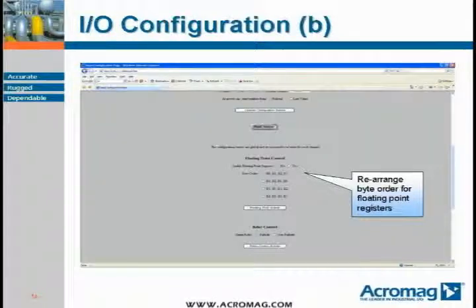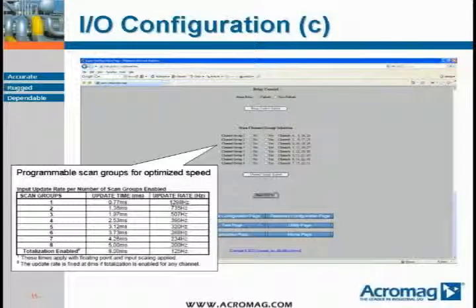By default, the output bytes for each channel are transmitted according to the IEEE 754 standard, but may be rearranged as desired. Scan groups may be set so that the unneeded channels are ignored to minimize the scan time for the unit. Notice the scan group table, which highlights the update times as more groups are enabled. 4 channels take 770 microseconds, and all 32 channels take just 5 milliseconds to scan.